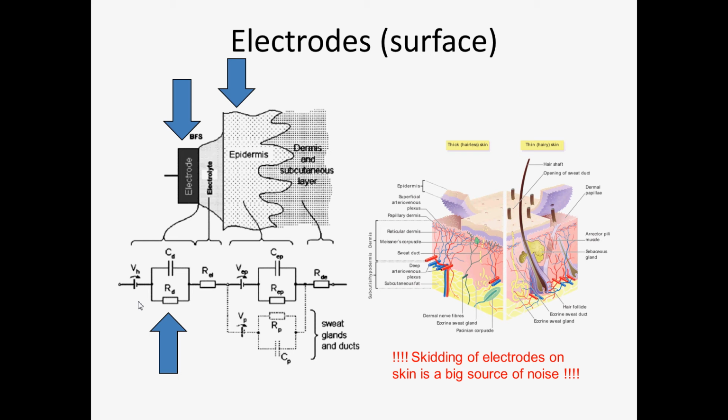Also, caps might not take into account the fact that somebody might have a head that is much more developed in one direction rather than another. The only way to make sure that you record EEG from always the same position, I'm afraid, is the long preparation of the head, which takes up to 3 minutes per electrode, because you need to apply your individual electrodes.